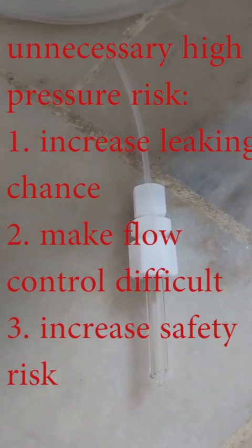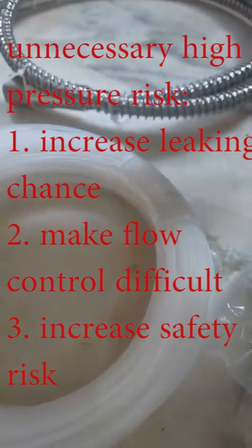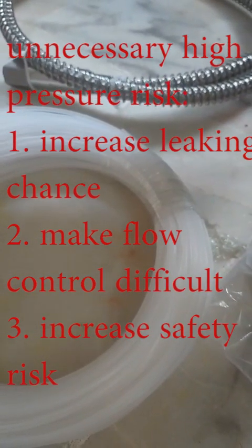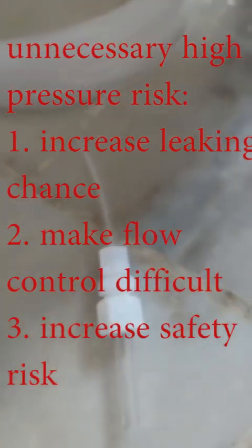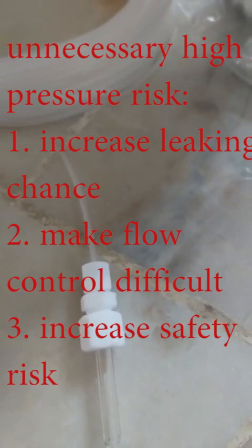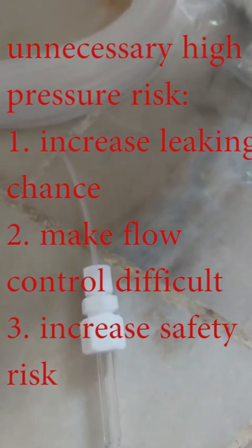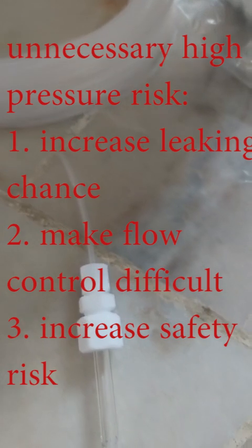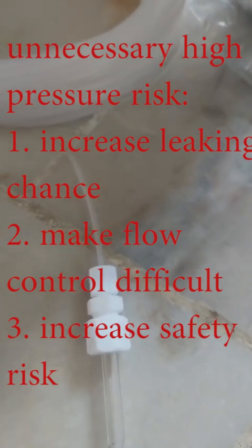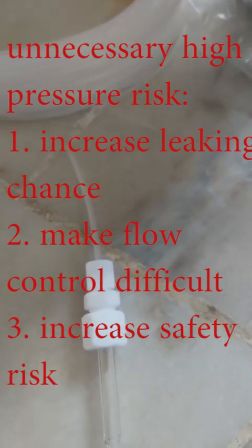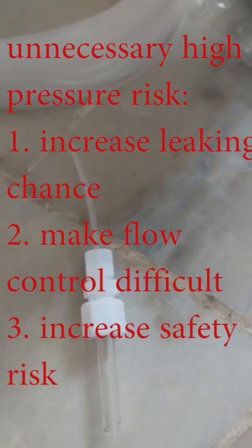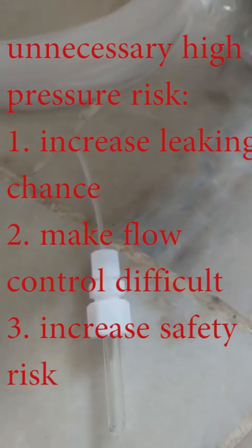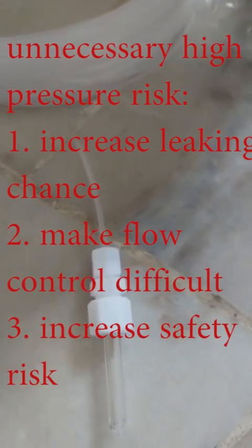Of course, if your device, like what we're doing, is installed with high pressure flexible tube, it will have no risk. But sometimes, like your old device, you are using not very professional tube connections, and high pressure gas sources may lead to strong leakage, which is the problem you faced.